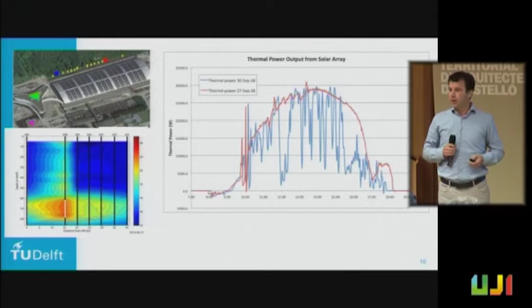Right now we're only providing about 100 megawatt hours a year to this facility, so the actual energy demand is much larger. But we can easily increase the number of PVT panels. There's enough space available in the aquifer to increase the heat storage for sustainable heat to the building. Maybe we need an extra well to meet the required capacity, but there's enough space available in the aquifer to do that.